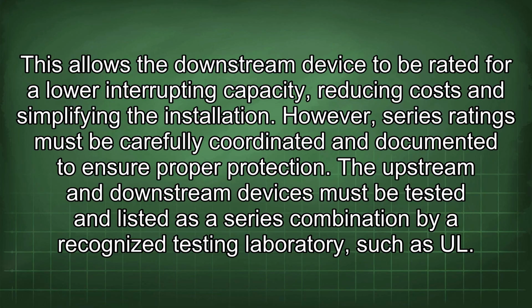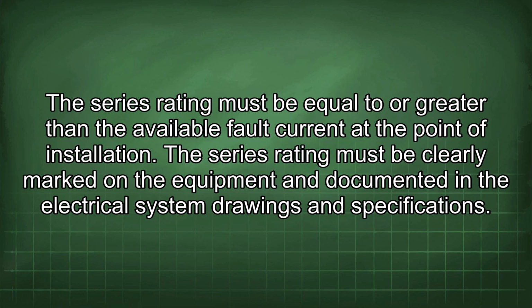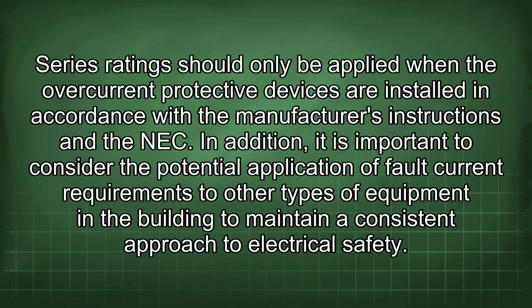The upstream and downstream devices must be tested and listed as a series combination by a recognized testing laboratory, such as UL. The series rating must be equal to or greater than the available fault current at the point of installation. The series rating must be clearly marked in the equipment and documented in the electrical system drawings and specifications.